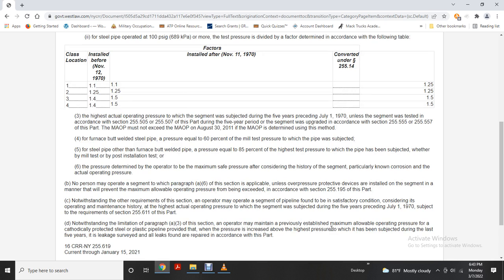The highest actual operating pressure to which the segment was subjected during the 5-year period preceding July 1st, 1970, unless the segment was tested in accordance with sections 255.505 and 255.507 of this part during that 5-year period, or the segment was upgraded in accordance with 255.555 or 255.557 of this part. The maximum allowable working pressure may not exceed the maximum allowable working pressure on August 30th, 2011, determined using the same method. For furnace butt welded steel pipe, the pressure is equal to 60% of the mill test pressure.